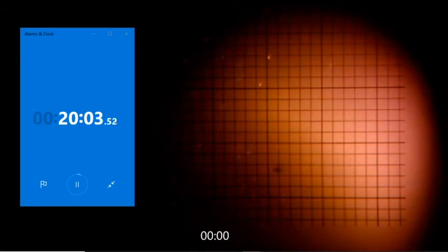257.4. Can you go a little bit higher? Yeah, you want to go 280? No, 260, like right around 260. Very hard. I don't know. I see. 261.3. Okay, fine. 260, 261.3? Yes. 261.3 volts.